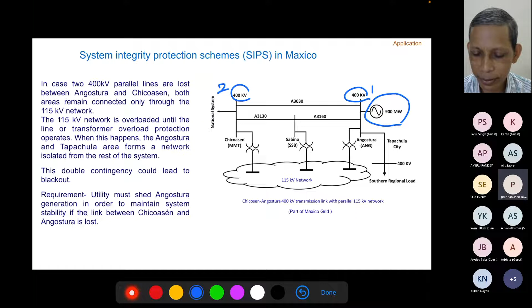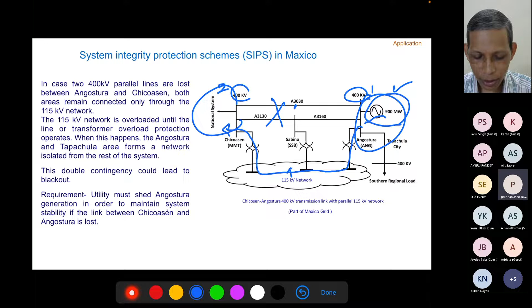Some transformers in this path are not designed for it and become heavily loaded. So if a transformer trips anywhere or the line trips, the corresponding power also cannot flow from one side to the other. This becomes challenging for management on both sides and leads to instability in the system. So what is being done is that in case the line trips, the generation here has to be reduced. That's the task.